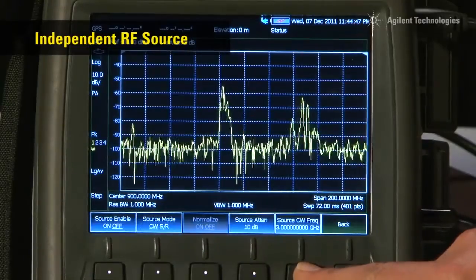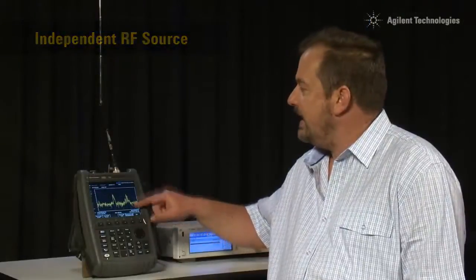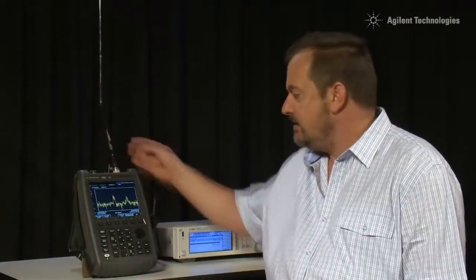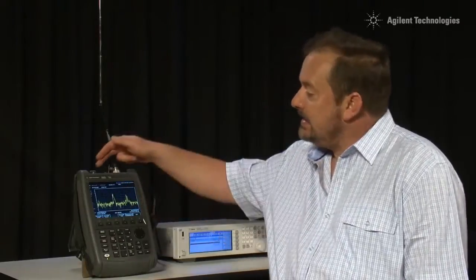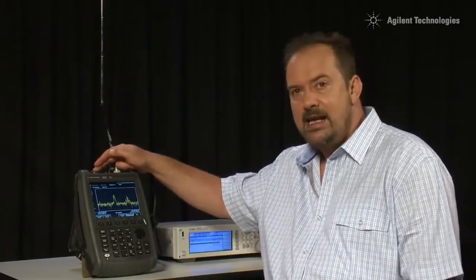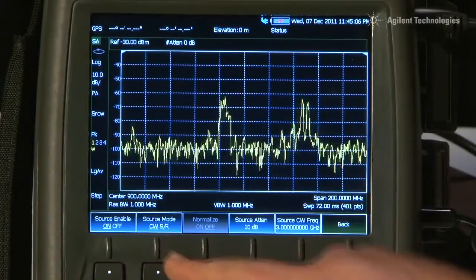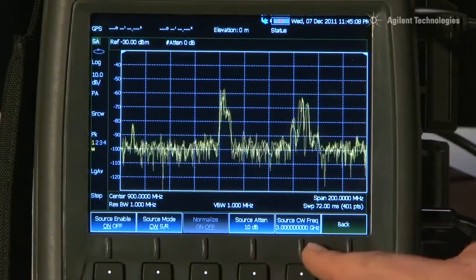One unique feature of the FieldFox is its independent source. Even though we are currently using the spectrum analyzer as a normal spec-an, with in this case an antenna monitoring some frequencies coming off air, the signal generator within the FieldFox can be used totally independently. In this case we have it turned on, it is being used as a CW source, and the frequency can be set completely independently.